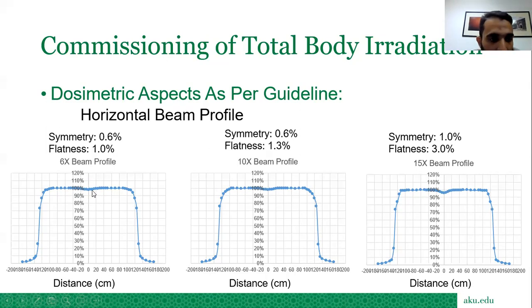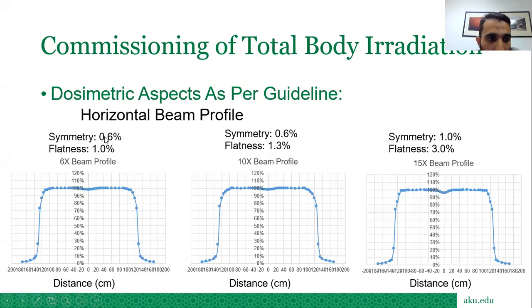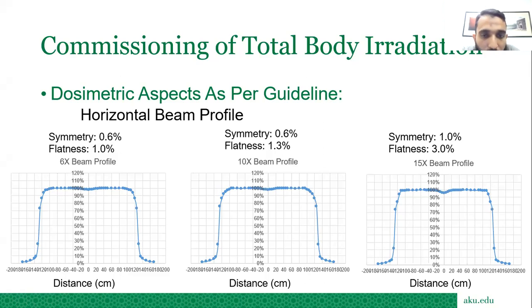The horizontal beam profile results: for 6X, flatness was 1% and symmetry was 0.6%; for 10X, flatness was 1.3% and symmetry was 0.6%; for 15X, flatness was 3% and symmetry was 1%. The 15X showed higher flatness deviation.